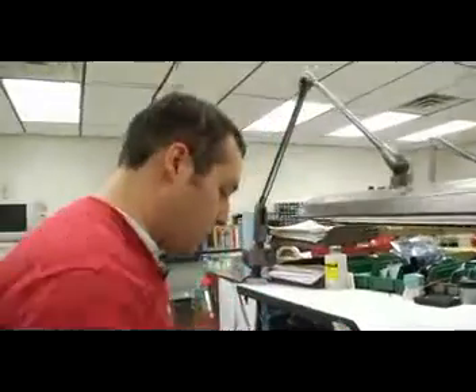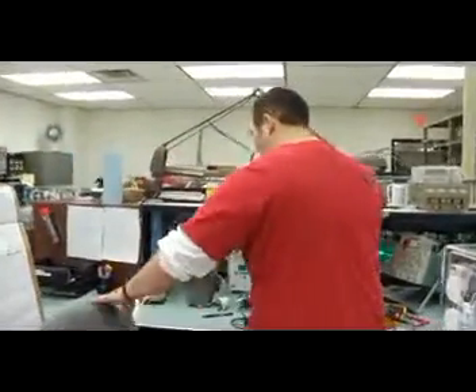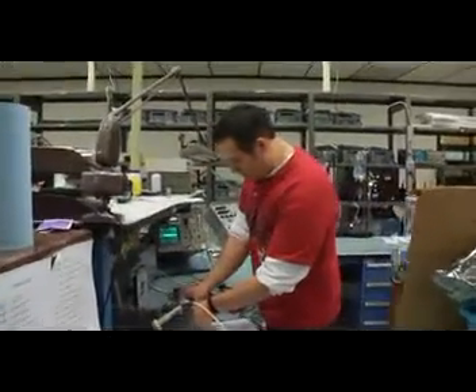This is a control board — it controls temperatures. I calibrate those, test them out, making sure everything works. I also calibrate the incubators themselves, make sure the heater and the display works out okay, making sure that the frequencies are right.